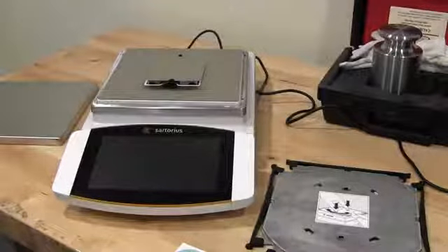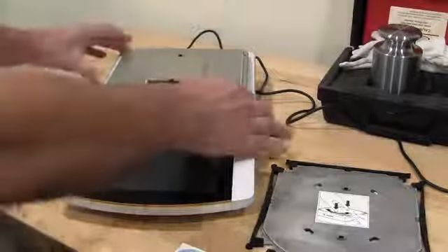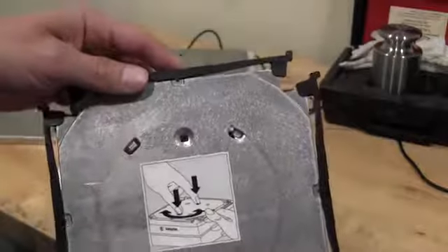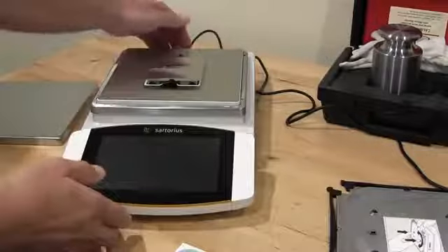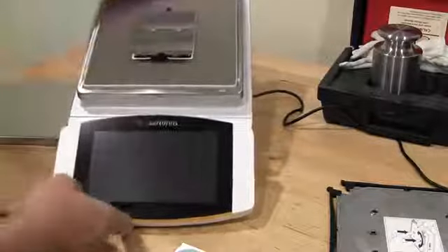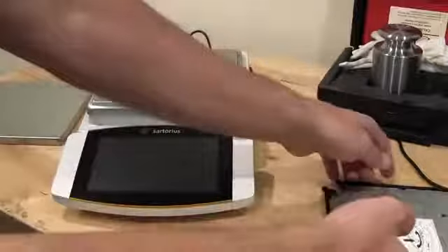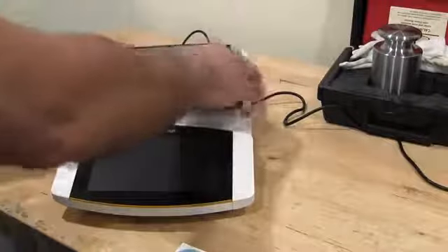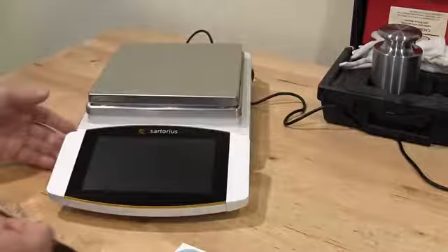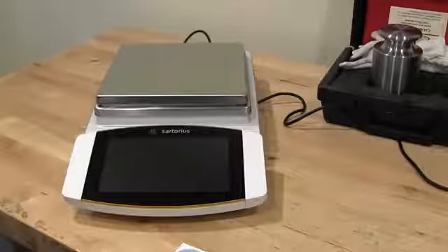When you get the balance and set it up, there's this little steel ring that has to go on, and then what's pretty unique is the pan support and how this clicks in. If you look, there's a groove here and here, and there's two holes. On this balance you'll see there are two plastic tabs, so it needs to lock in. You simply take this platform, put it on there, turn, and it locks in place.